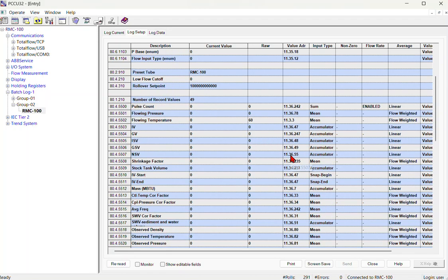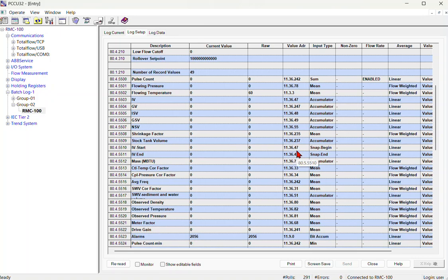On that side, let's say that you have the Coriolis going to the PLC versus the total flow in this case. As long as you can send over the Modbus, there'll just be a slight delay. But as long as we can do the volume flow rate, the density, temperature, and pressure, if we can Modbus those four values out, you can just set up a dummy tube here and then do all this locally on that side.